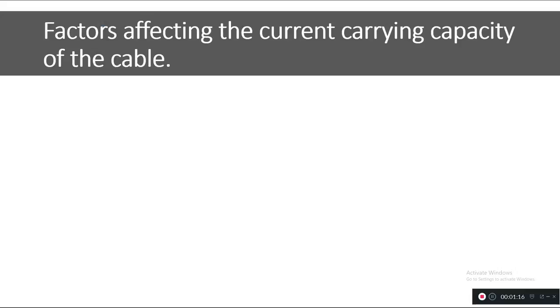Before starting with the calculation, I would like to tell you about the factors which affect the current carrying capacity of a cable. The first factor is temperature. The ambient temperature affects the current carrying capacity. For example, if the temperature is more than 35°C, the capacity decreases, whereas if it is less than 25°C, the capacity increases. We need to refer to the cable manufacturer's datasheet to get the correction factor for our operating temperature conditions at the site.